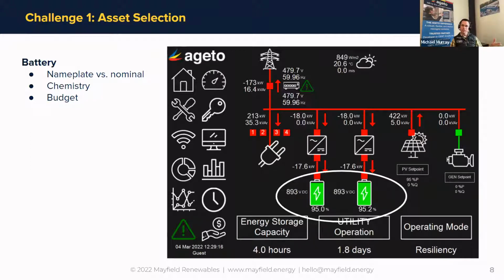Usually these projects, and especially off-grid microgrids, need at least a 2-hour discharge for a standard C&I microgrid application, but some unique applications only need 20 minutes of backup power. So there you could get away with a 2C or a 3C battery, which can save money. Another thing to look at is beginning of life versus end of life. The beginning of life rating is how much energy you have when new, and end of life is after 10 years. So typically in the C&I space, commercial industrial, we're looking at beginning of life, with end of life calculations more common in utility scale projects.